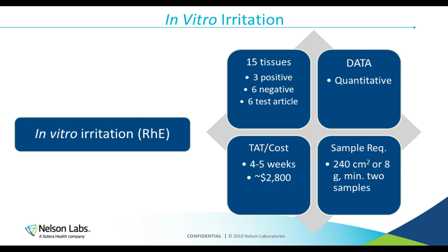So we'll go through this like we did for the in vivo. So our extraction is very similar. It's identical, actually, to the in vitro or to the in vivo method. We still want to use your final finished device if that's what's available. We'll put that in an extraction container, do a polar and a nonpolar solvent, and then preferably use 50 degrees for 72 hours. The exposure. So this is where we take that extract after it's been extracted in the incubator and we put it on the tissues. So that is applied topically.